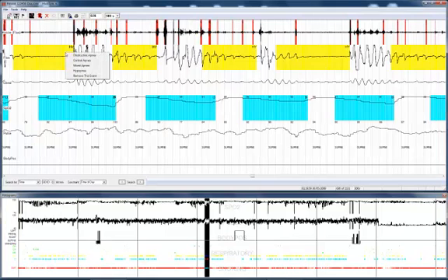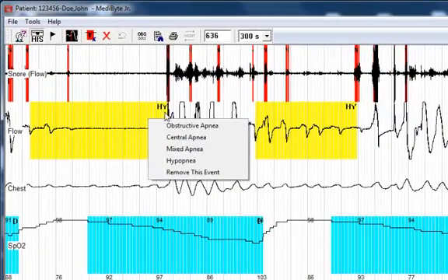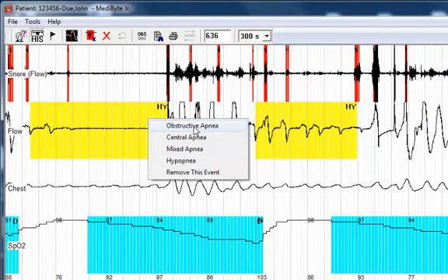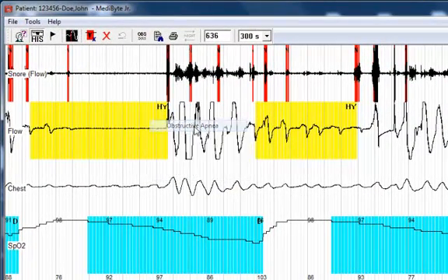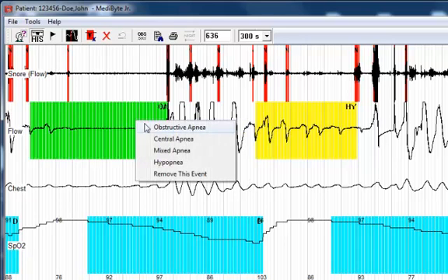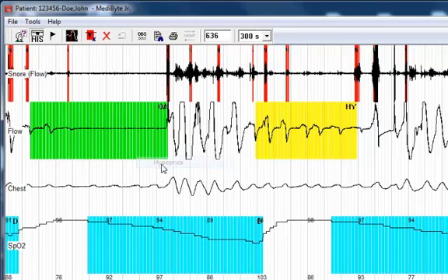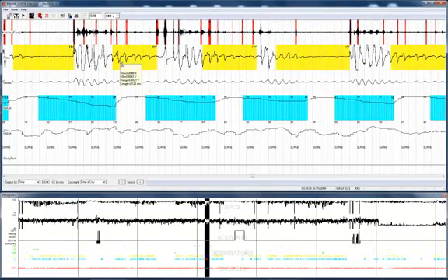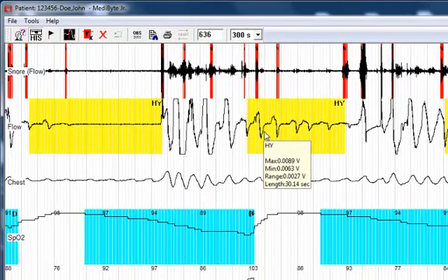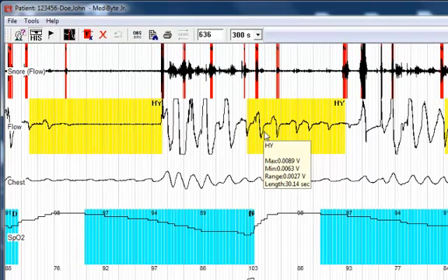You may change the events on the screen by right clicking. For example, if I wanted to change this from a hypopnea indicated as HY to an obstructive apnea, I simply select obstructive apnea. I may change it back, right click. If you do a mouse over on the event, it will actually indicate the maximum voltage, the minimum, the range, and the length in seconds. For example, if I do a mouse over on this saturation event, it indicates that the maximum arterial oxygen saturation is 98%, the minimum is 86%, that's a 12% drop.